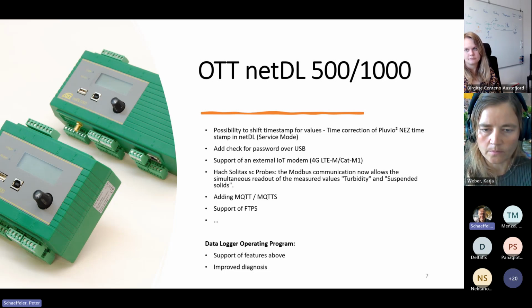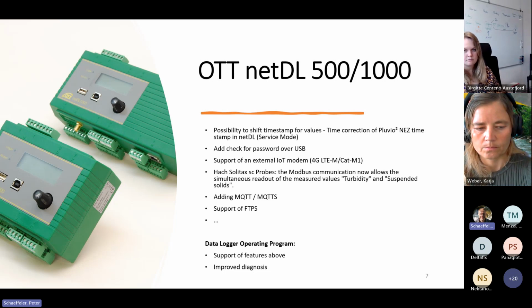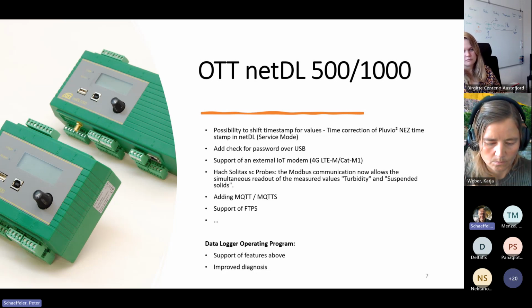One feature is the possibility to shift the timestamp for values, a time correction of the Pluvio² timestamp in NetDL. This was a request from larger services, since the Pluvio² takes 5 minutes to take a measurement in a certain configuration, and there was a need to adjust the timestamp in the NetDL. This is now possible, but only in service mode, not officially available to everybody. The reason is we don't want somebody messing up timestamps. But if you need that, go to service mode, and if you need support, HydroService can tell you everything about it.